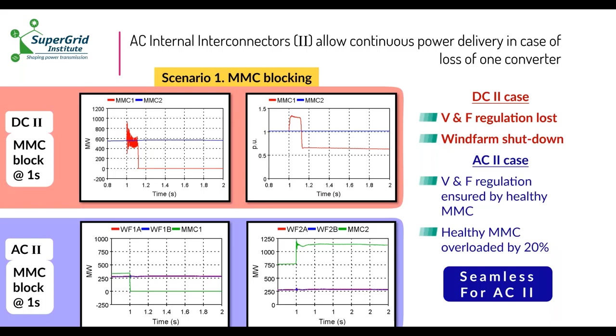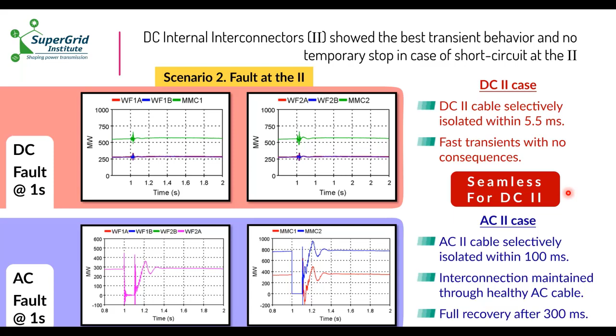...pass from one wind farm to the other because there is redundancy of AC cables. For the fault at the interconnector, in the DC case, it is seamless because you have a fault on the line and it is selectively and rapidly isolated by the DC breaker, so you can still operate. But in the AC case, the AC breaker is slower, so you have a loss of power during 100 milliseconds, and some transients after. So it's seamless for DC.